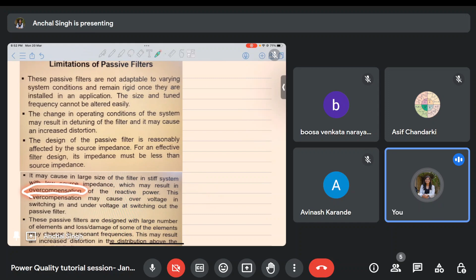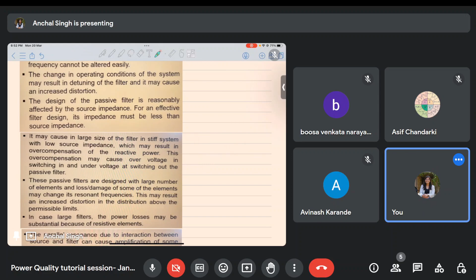And in case, so when we design these filters, we normally design them for full load condition. But what happens is when my system is not operating at the full load condition, then eventually I am providing overcompensation to my system. So in that case, when the filter gets connected, then my point of common coupling voltage increases, and if I take my filter out, then my point of common coupling voltage decreases. So because of that overcompensation problem, the whole purpose of putting this filter was to take care of the power quality problem, right? Harmonics. But it itself is giving other power quality problems of voltage distortion, which is not at all what we want, right? These are a few of the drawbacks of these kind of systems.